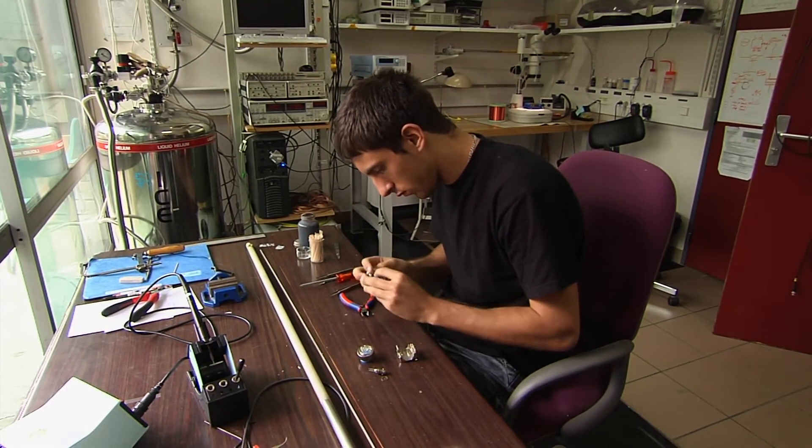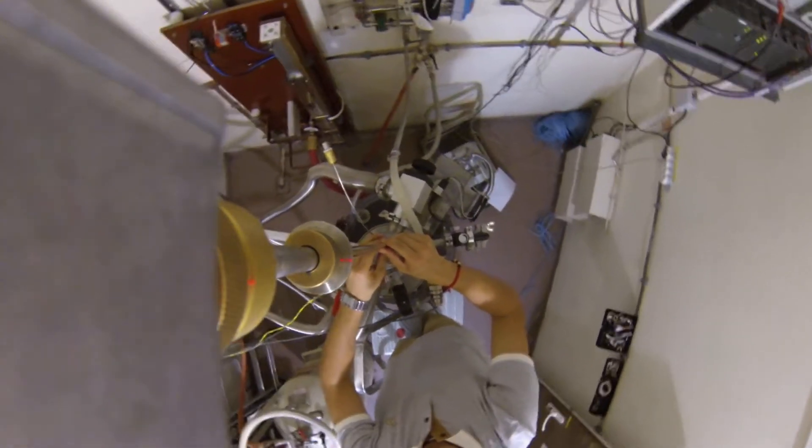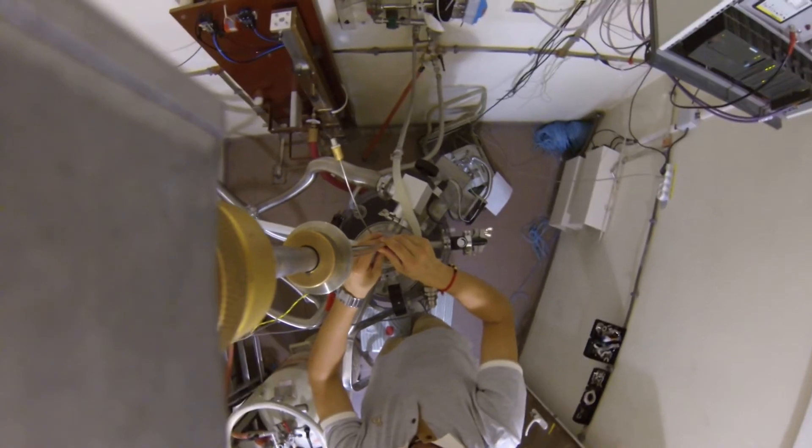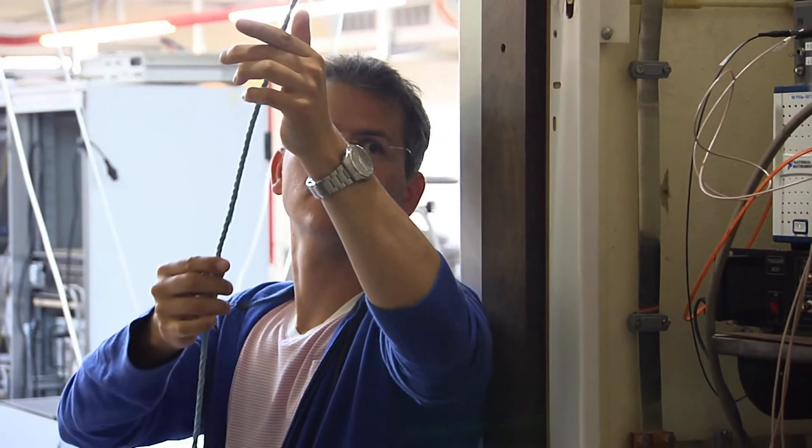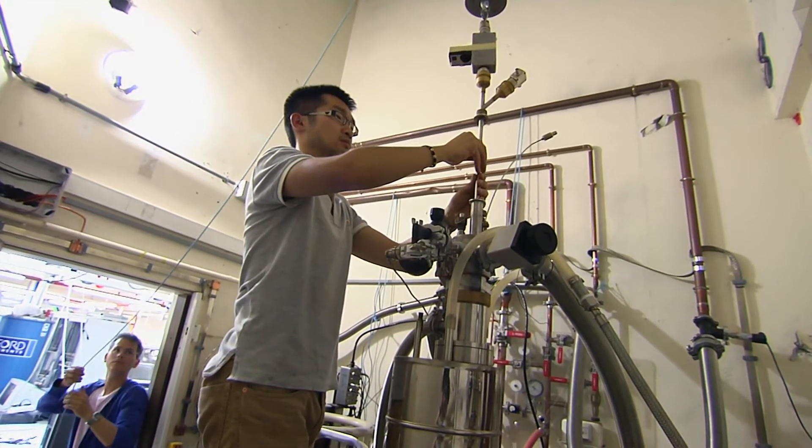And then the probe goes into the cryostat. The cryostat is placed in the magnet and then the sample is really placed in the center of the magnetic field and it's cold due to the surrounding of liquid helium.